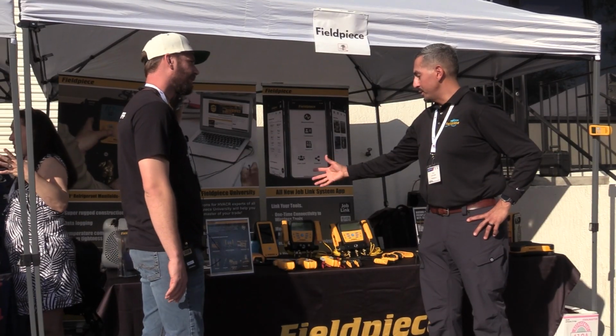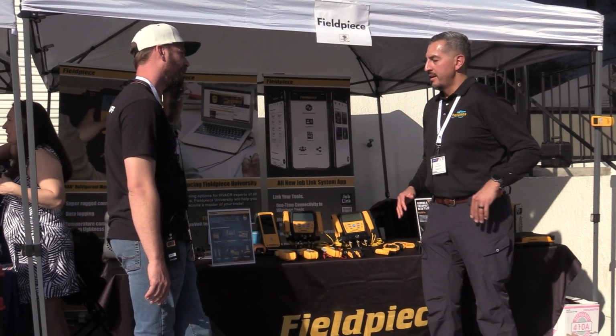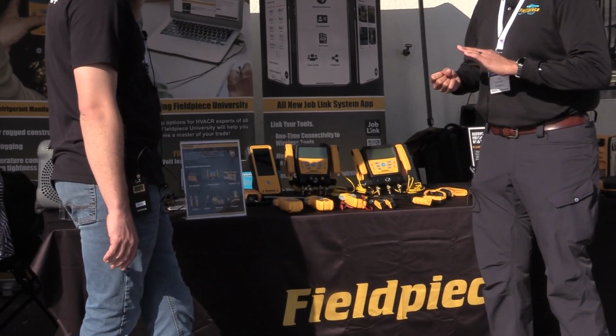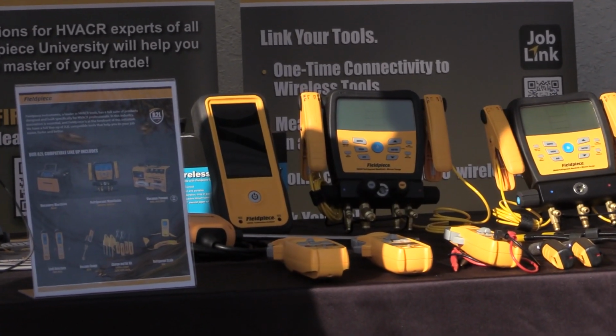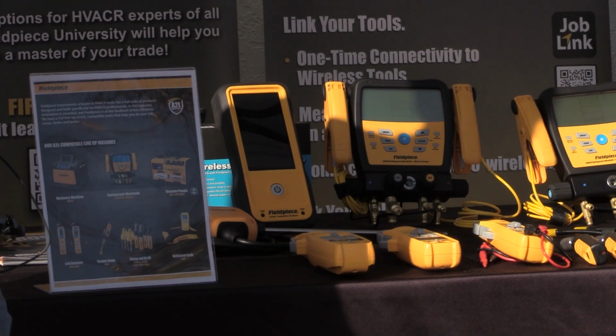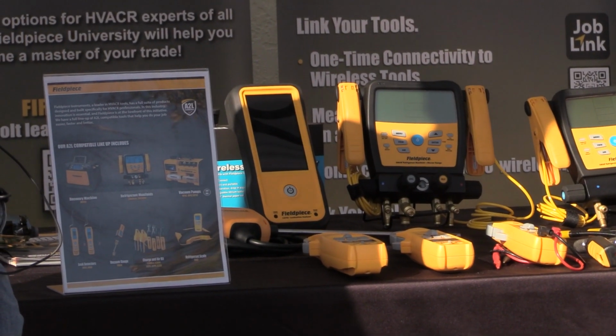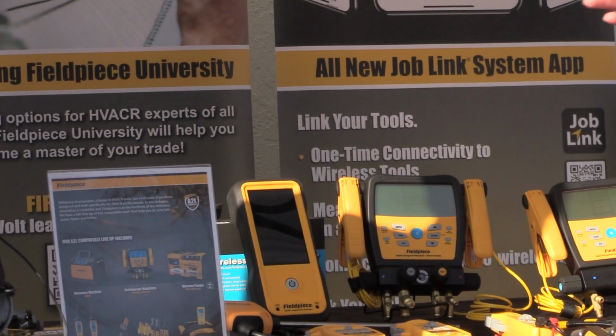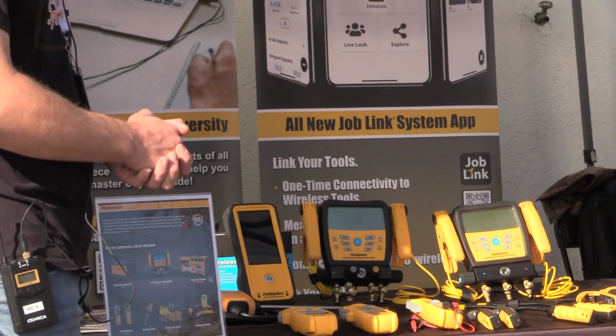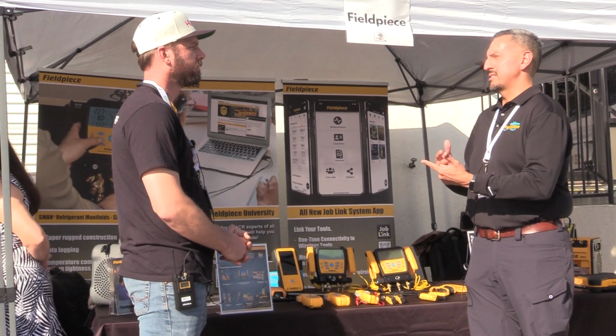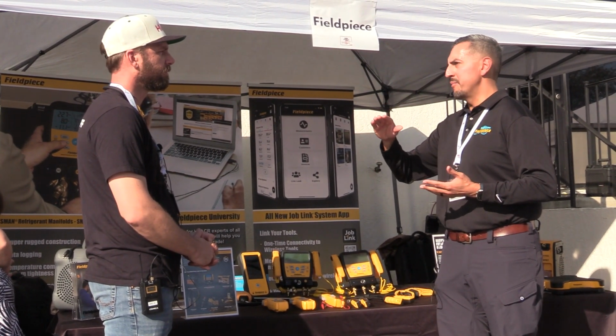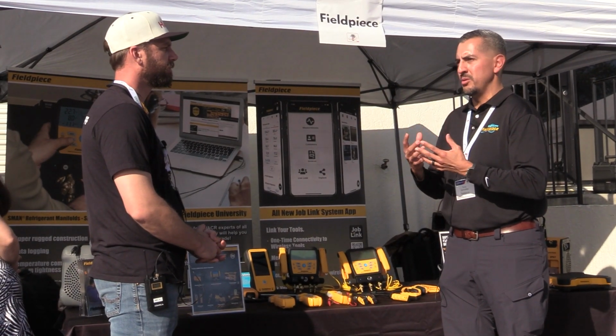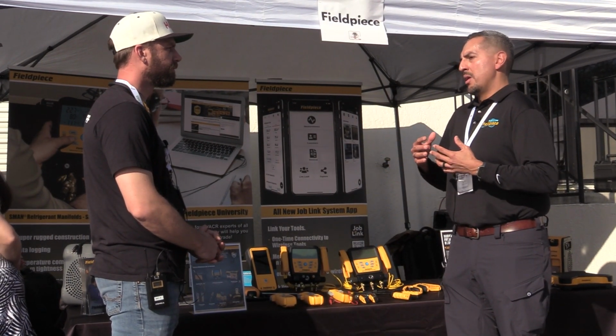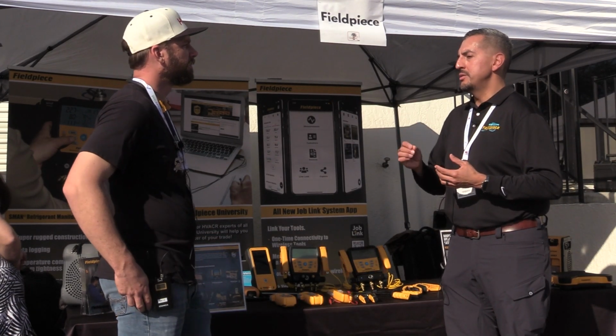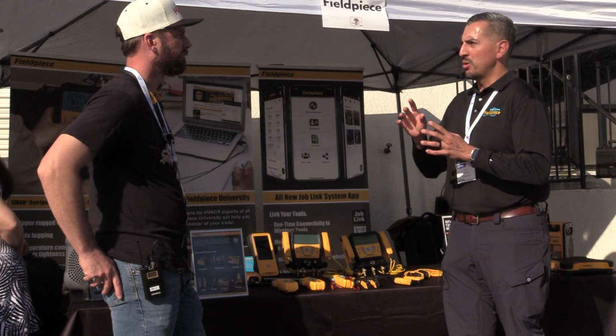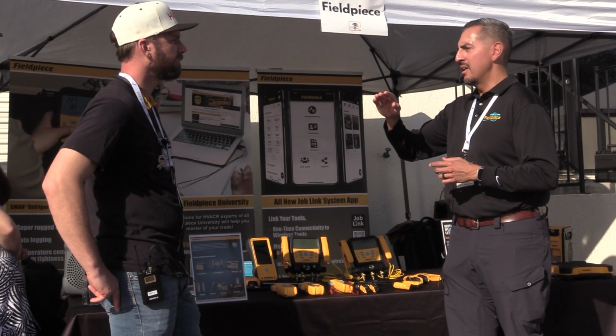We introduced two versions of our combustion analyzer. They're both designed to lower the overall cost of ownership of having a combustion analyzer and maximize its uptime. What does that mean? Well, combustion analyzers typically have some type of oxygen sensor and a carbon monoxide sensor, and we know those sensors degrade over time just by being exposed to the oxygen in the air. In the past, whether you're using your tool or not, that didn't pause the degradation on those sensors.